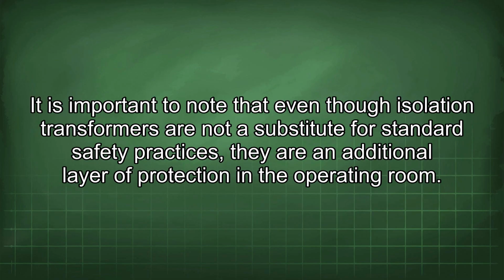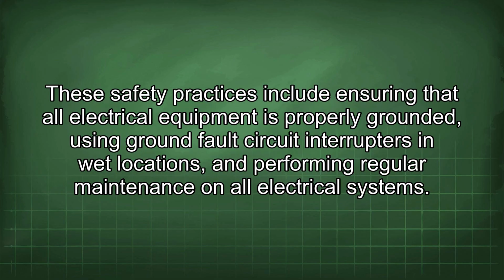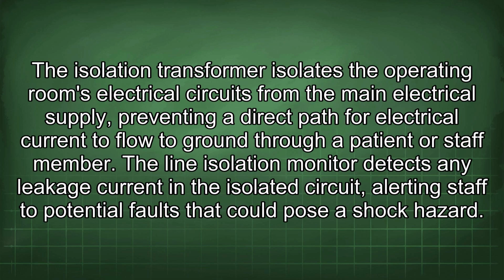It is important to note that even though isolation transformers are not a substitute for standard safety practices, they are an additional layer of protection in the operating room. These safety practices include ensuring that all electrical equipment is properly grounded, using ground fault circuit interrupters in wet locations, and performing regular maintenance on all electrical systems. The isolation transformer isolates the operating room's electrical circuits from the main electrical supply, preventing a direct path for electrical current to flow to ground through a patient or staff member.